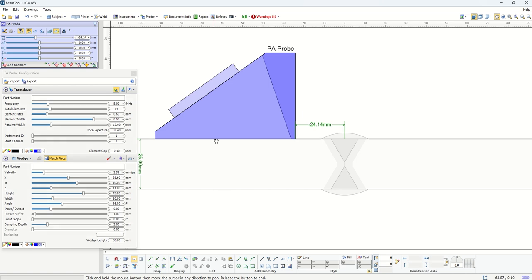The first step is for us to choose what probe and wedge we want to use for this scan plan or inspection. This is where people generally refer to what they have in their inventory, or a specific idea of what type of probe and wedge would be appropriate. For this example, I want to demonstrate the use of a common 64-element probe, 5 megahertz A12 from Evident, which is basically a 5 megahertz, 64-element, 0.6 pitch probe.